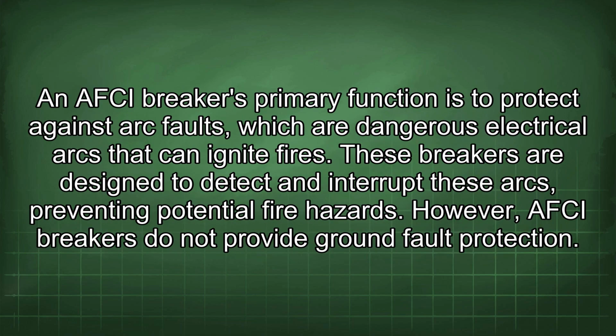An AFCI breaker's primary function is to protect against arc faults, which are dangerous electrical arcs that can ignite fires. These breakers are designed to detect and interrupt these arcs, preventing potential fire hazards. However, AFCI breakers do not provide ground fault protection.